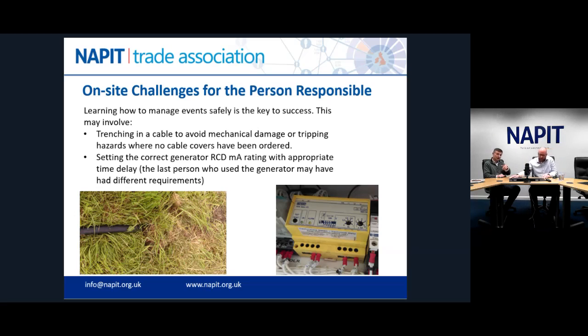Yeah, and also just quickly on this point, one thing BS 7909 also talks about may sound like electrical heresy, and that's turning RCDs off. Because in an event, you have to think about the application of crowd control, so that if you've got 50,000 people in a field and an RCD trips, then you might have a crowd control issue as 50,000 people start stampeding for the exits. So BS 7909 recognises that and says in some situations it may actually be safer to turn an RCD off to avoid that level of risk happening in an environment where you've got a lot of people. And that would be quite a new concept to some of the viewers here today.